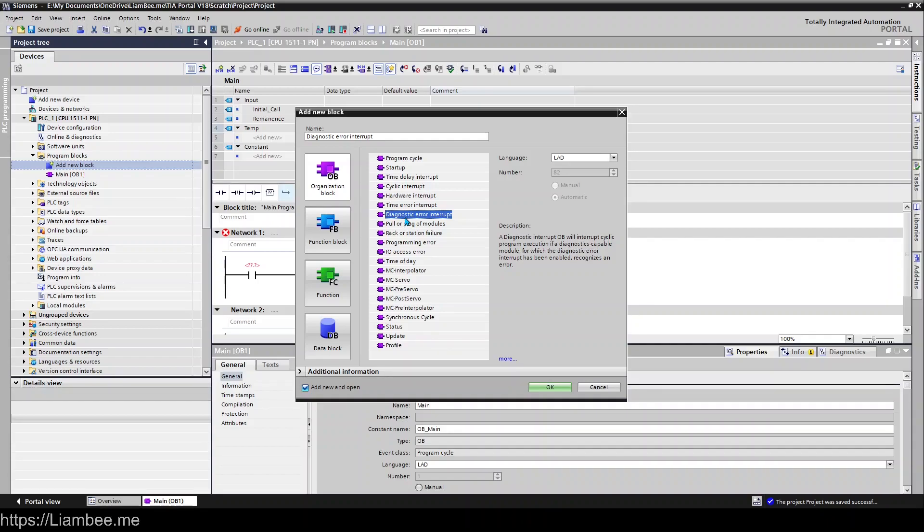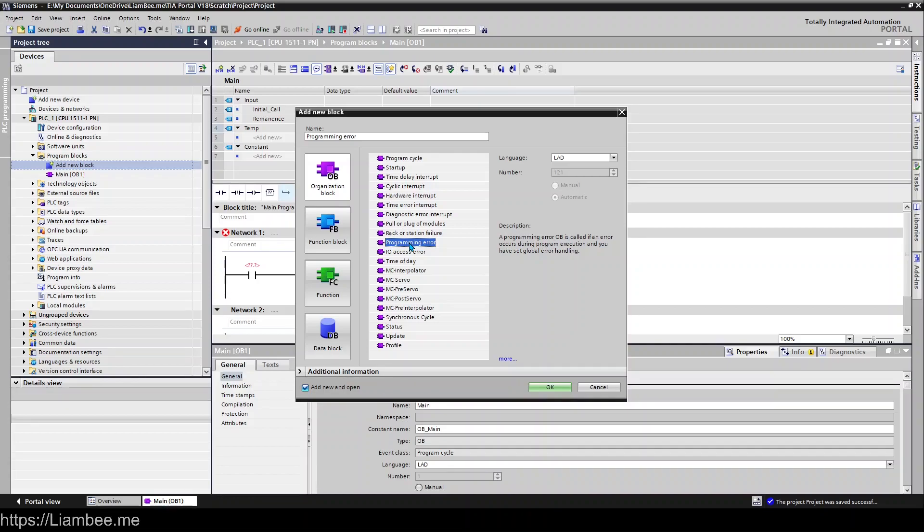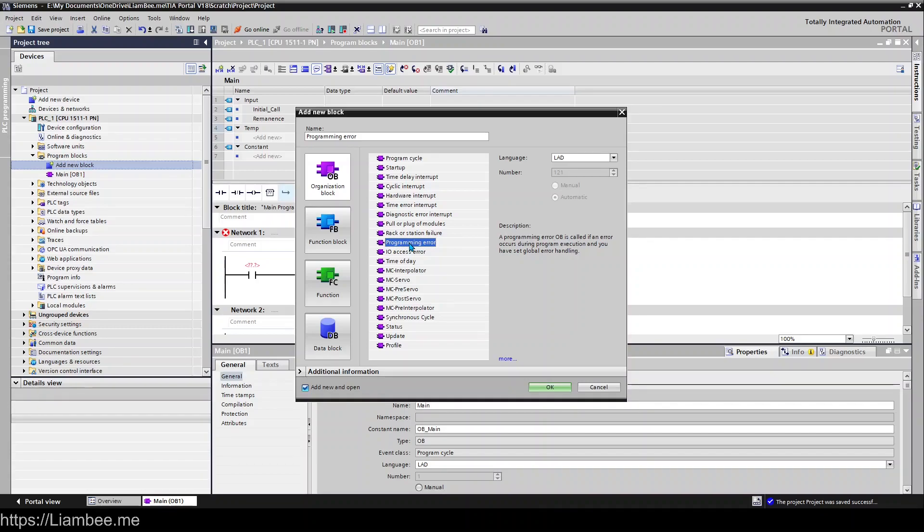Programming Error. This is a great one to put on when you are building your project, especially if you're new, because there'll be a lot of times where you forget to put something on an interface or something like that and the PLC will just stop and you'll be told in the diagnostics what the error is. But sometimes it doesn't matter, you know you're testing something else and what you want to do is just have the PLC running whether there's a fault or not. So having Programming Error in there is great.